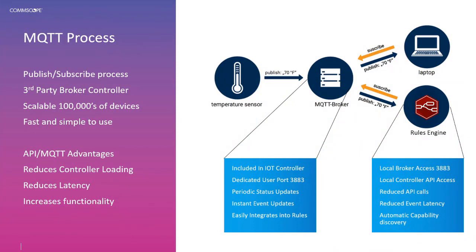The key thing with MQTT is that it is a subscribe-publish process. The sensor generates information, that information is published to a broker, and the broker then sends that information on to anybody who wants to subscribe to that same data. The MQTT broker runs within the IoT controller and is provided on a dedicated user port of 3883, providing updates whenever information changes on any of the sensors or devices attached to the IoT controller.